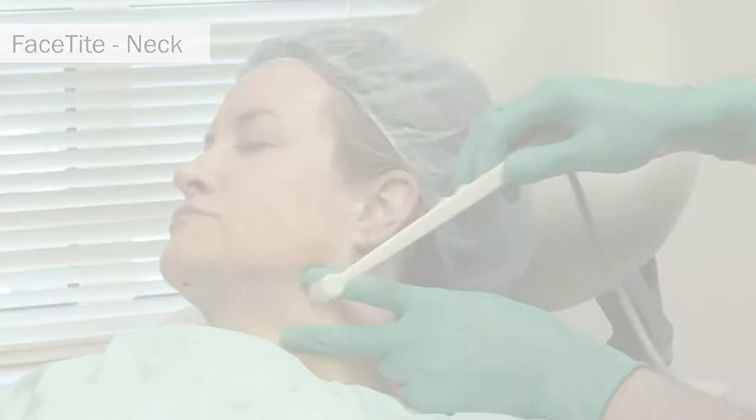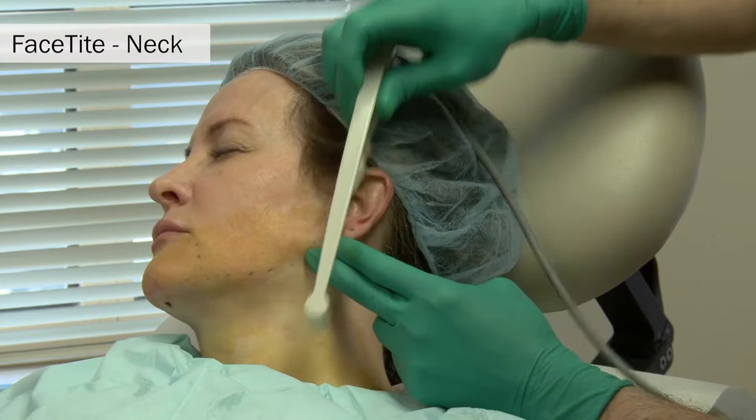This is a look at the FaceTite handpiece, consisting of a subdermal 10-centimeter probe and surface bipolar electrode. Dry passes are made through the porthole laterally to allow the probe to slide underneath the surface of the skin in a pre-platysmal fashion. This ensures that the probe does not get hung up on the fibroseptal network underneath the skin as it is passed when heat is applied.